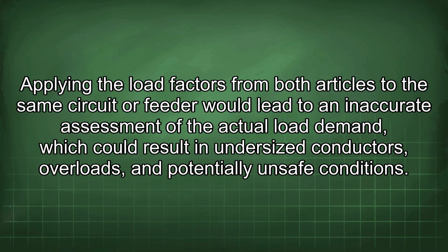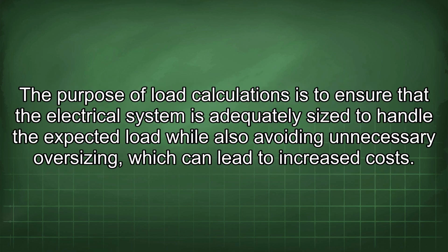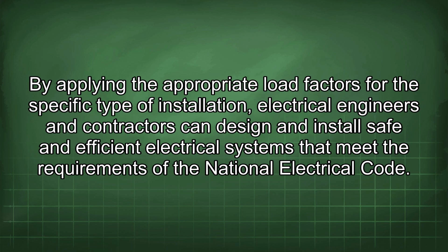Applying the load factors from both articles to the same circuit or feeder would lead to an inaccurate assessment of the actual load demand, which could result in undersized conductors, overloads, and potentially unsafe conditions. The purpose of load calculations is to ensure that the electrical system is adequately sized to handle the expected load while also avoiding unnecessary oversizing, which can lead to increased costs. By applying the appropriate load factors for the specific type of installation, electrical engineers and contractors can design and install safe and efficient electrical systems that meet the requirements of the National Electrical Code.